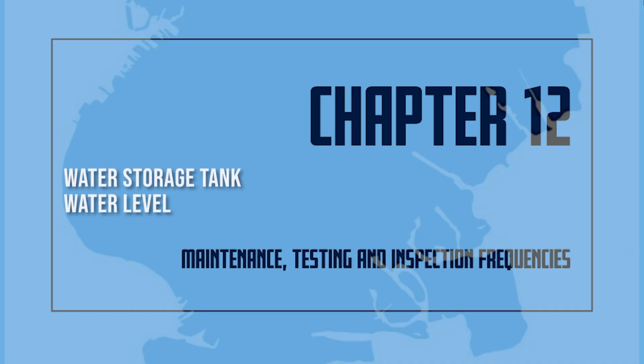C. Water storage tank. Condition of water in tank. Water level. Tanks without supervised water level alarms at constantly attended locations shall be inspected monthly. Tanks with supervised water level alarms at constantly attended locations shall be inspected quarterly. Water temperature. The temperature of water tanks shall not be less than 40 degrees Fahrenheit.